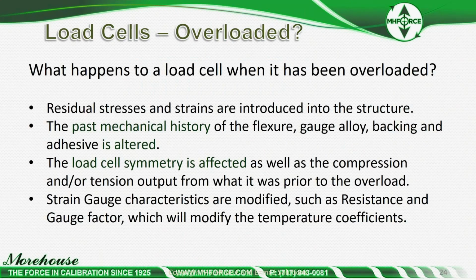So what happens when they overload it? Well, residual stresses and strains are introduced into the structure. The past mechanical history of the flexure, gauge alloy, backing, and adhesive is altered. The load cell symmetry is affected, as well as the compression and or tension output from what it was prior to the overload. Strain gauge characteristics are modified, such as resistance and gauge factor, which will modify the temperature coefficients. So effectively, if that overload is showing at that 8%, there's a good chance that the temperature coefficients are shot and that load cell is no longer as good or has the temperature compensation it once had.